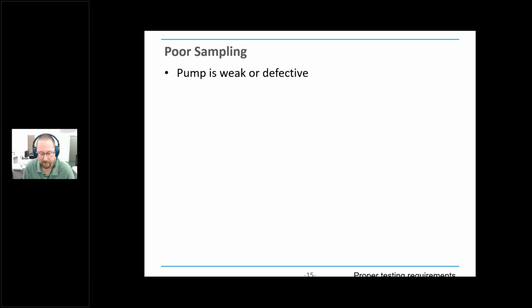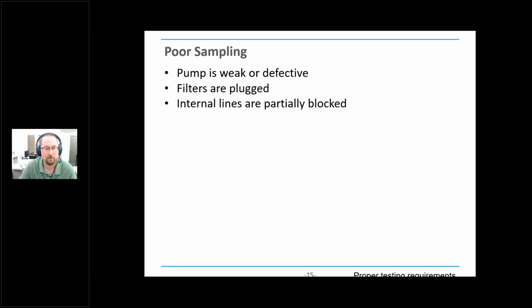So you get poor sampling. About 80% of all the gas monitors out there are what we call side stream, where they just sample a small portion of the breath being exhaled. They've got a pump in them. The other kind is on-airway or mainstream, where everything they exhale goes through a bigger device on the breathing circuit. Those are a much smaller percentage of devices out there. So in these side stream ones, your pump can become weak or defective, pulling in either too small a sample or no sample at all. And so you really need to make sure that that pump's working. It can also be due to plugged filters or partially blocked lines within the device.